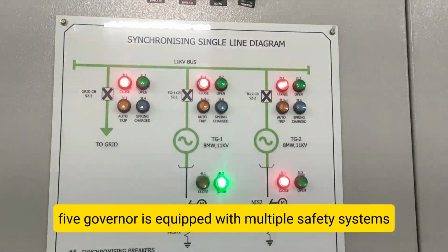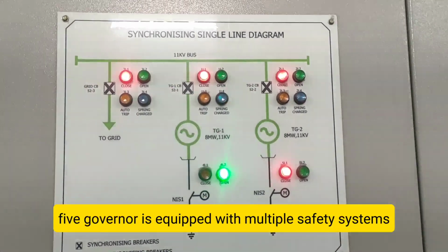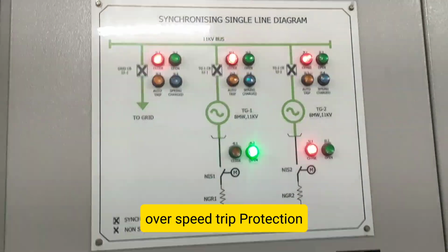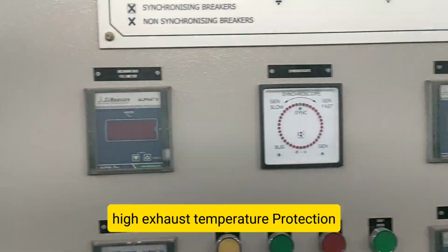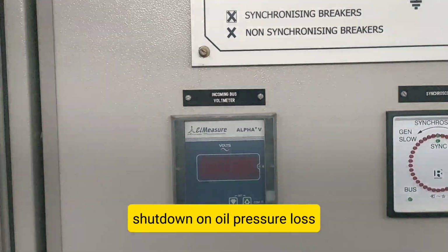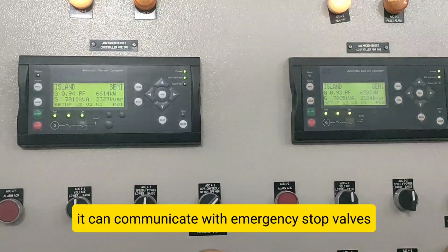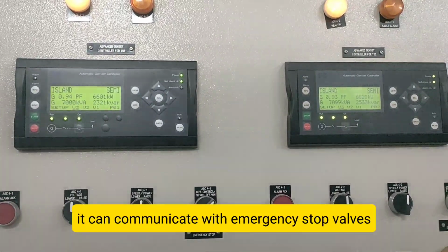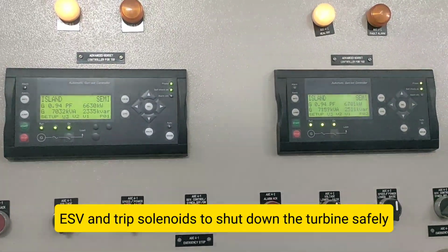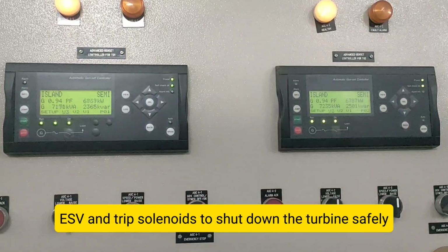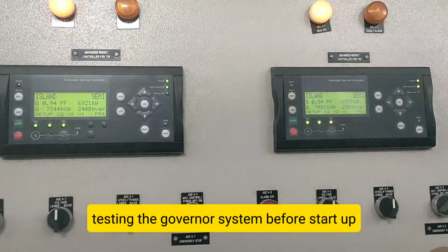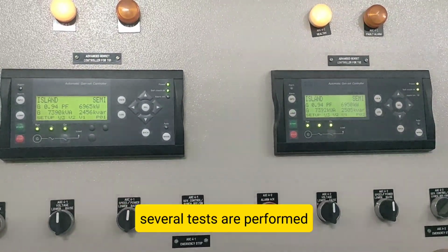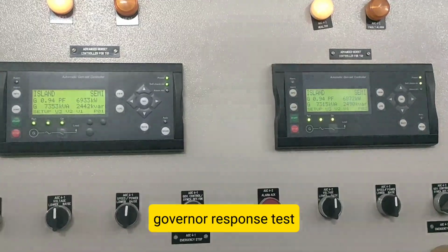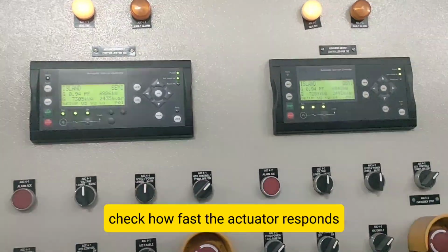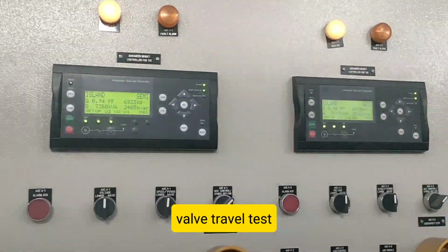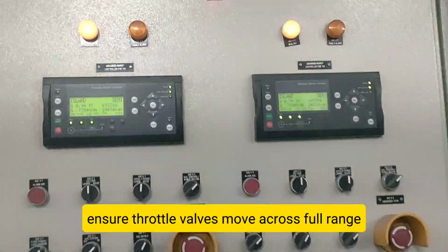When the generator is synchronized to the grid, electrical load demand varies constantly. The 505 Governor ensures load is maintained by adjusting steam flow to match the electrical output. For example, if load increases suddenly, like more motors start running, the Governor increases steam input by opening throttle valves. If load drops, it reduces steam flow. This helps maintain frequency stability and avoid overloading.